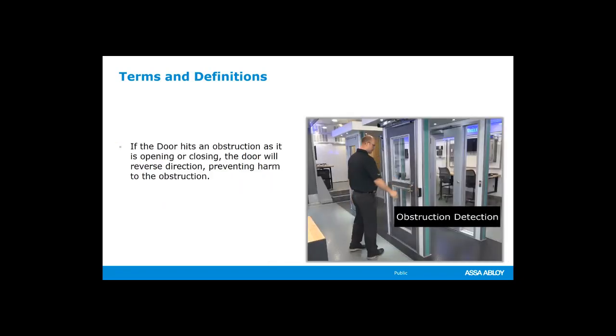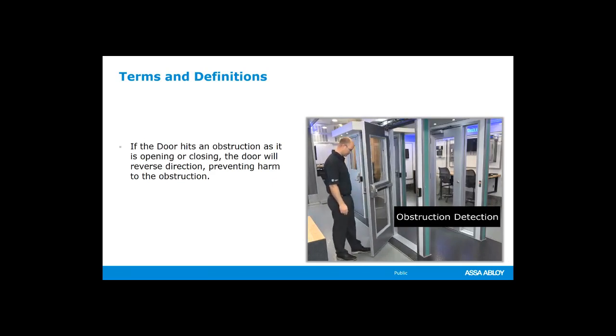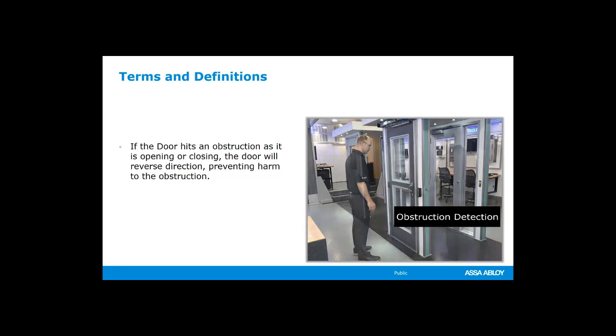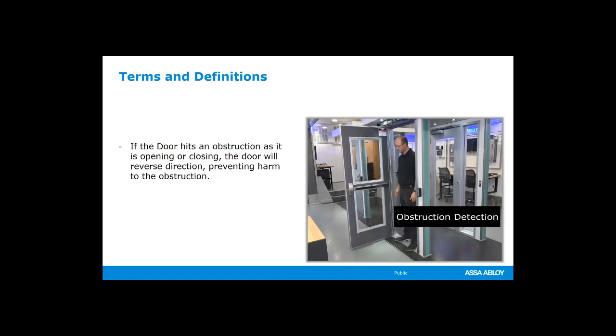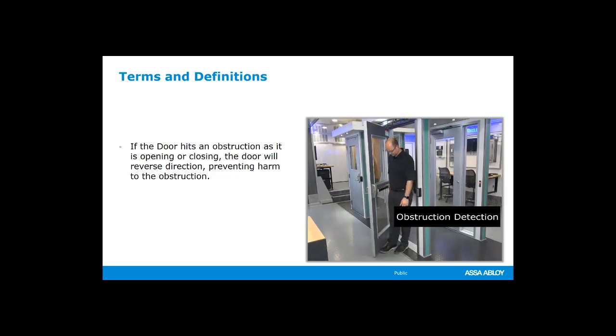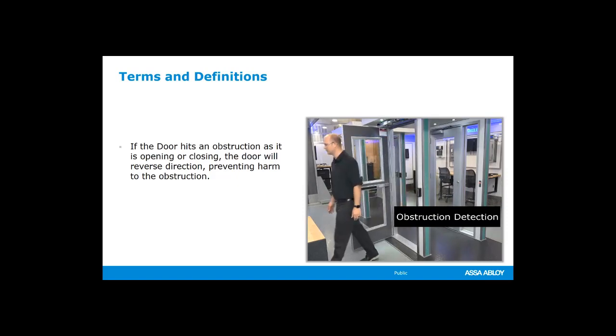Let's talk about obstruction detection. I've been very impressed with the obstruction detection capabilities of the 6300. It can sense obstruction on both the opening and closing motion of the door, and we can adjust how long the operator pushes on an object before it deems it an obstruction — from about one and a half seconds up to around seven seconds. The door is remarkably lightweight; it doesn't push against an object very hard before triggering obstruction detection. Many of these settings are adjustable.